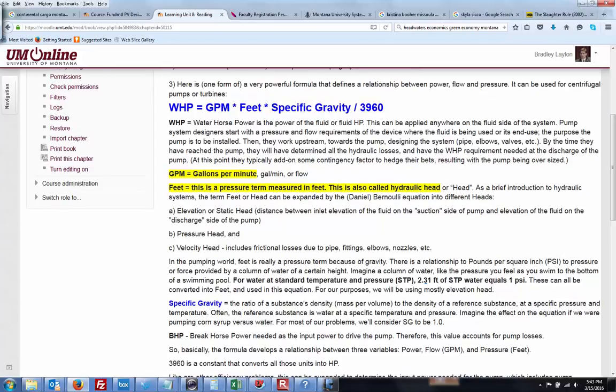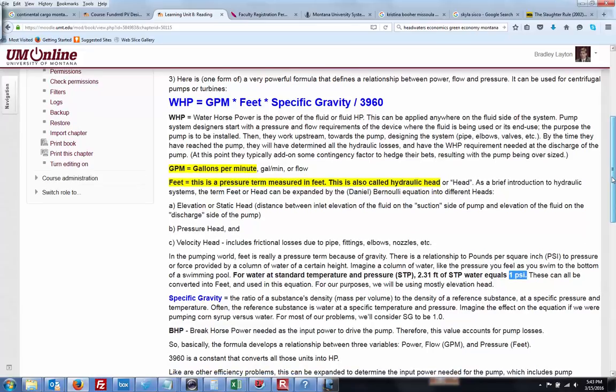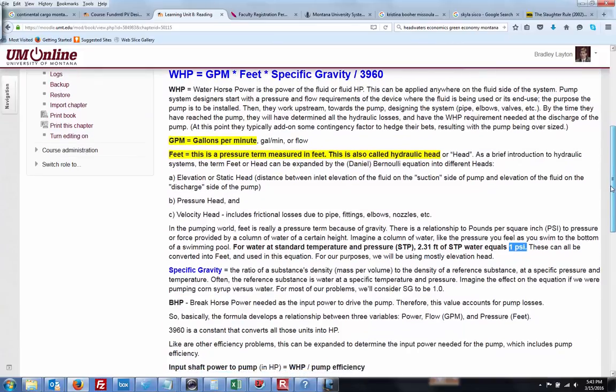Okay, 2.31 feet is 1 psi. Sounds about right. A pound of water that's 2.3 feet tall, 1 psi, 1 pound per square inch. Okay. Oh, that's what I was missing. Specific gravity is 1 for water. Very easy. The brake horsepower, that's what you need to drive the pump. So it's sort of the losses, whatever things sort of eating up in friction. Yeah. There we go. 3960 converts to horsepower.